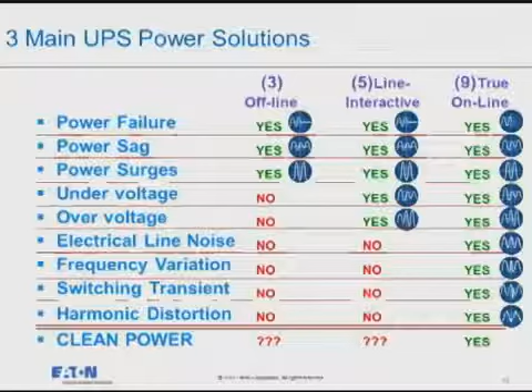The first, an offline or level 3, addresses, well, we could say they all address the obvious ones, right? And that has typically been, hey, as long as you address these three, you can be called a UPS. The reality of it is, though, we do have other power problems we need to consider. A line interactive or a level 5 addresses over and under voltages, but then stops. A true online will address all of them. So if you want to guarantee clean, filtered, regulated power, you almost have to go with an online double conversion technology. Well, let's see why.